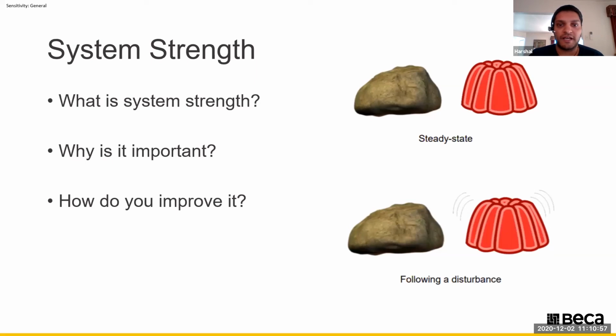The first consideration is around system strength. So what exactly is system strength? Some define it as a measure of the network's ability to maintain voltage levels during fault conditions. It's a combination of system inertia and system short circuit ratio, governed by the availability of generation to system fault level. It's important because it enables the network to maintain voltages during disturbances and faults, and keeps generation connected. I've always struggled to really understand what system strength is, and I've found a nice rock and jelly analogy to explain it in layman's terms.